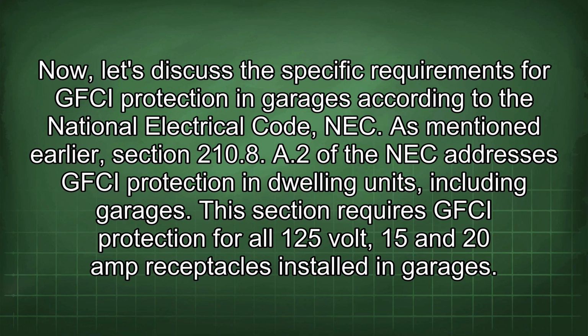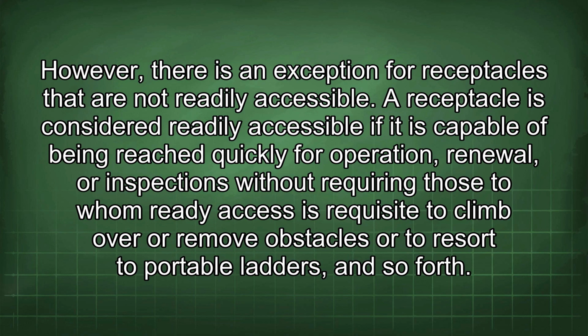As mentioned earlier, Section 210.8(A)(2) of the NEC addresses GFCI protection in dwelling units, including garages. This section requires GFCI protection for all 125-volt, 15 and 20 amp receptacles installed in garages. However, there is an exception for receptacles that are not readily accessible.